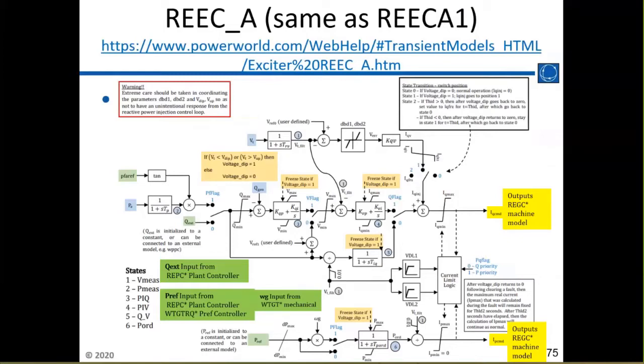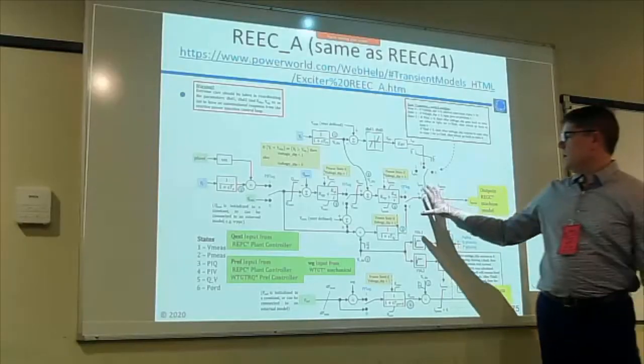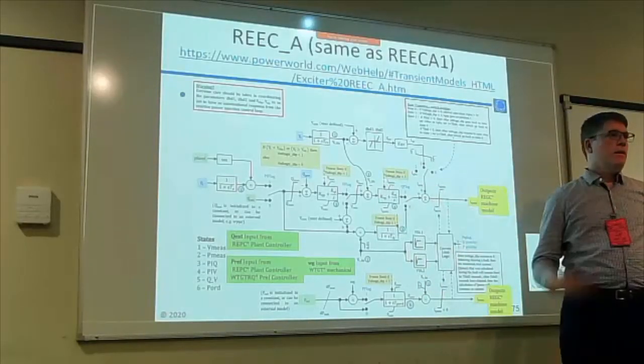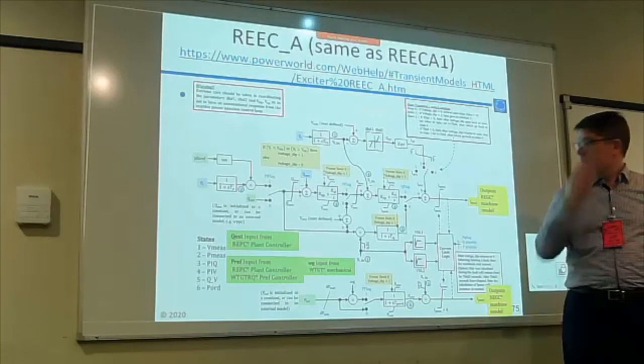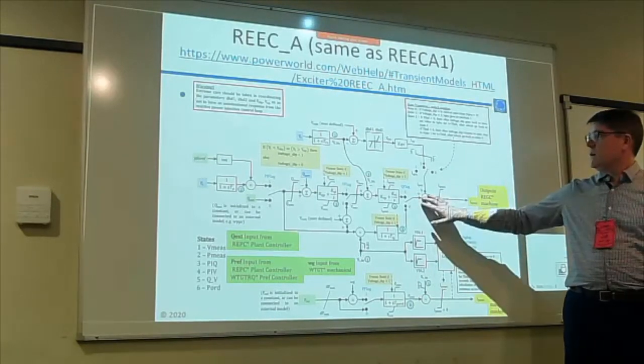And what's going to go on with the REEC model is it's going to be looking at its terminal. So it's doing the local control, trying to control the constant power factor here or voltage here. It's right there at each turbine. That's what this is meant to represent. And depending on how you set the flags in here, you get voltage or constant power factor.